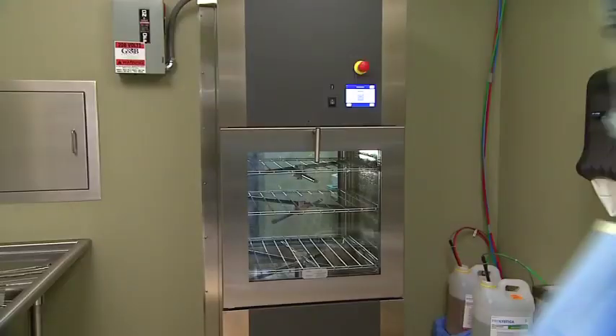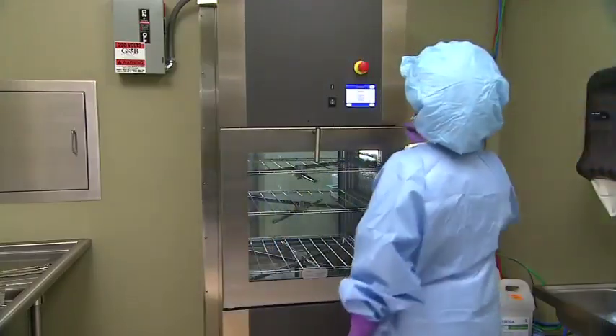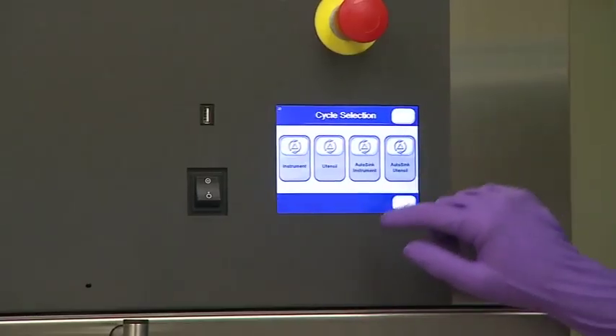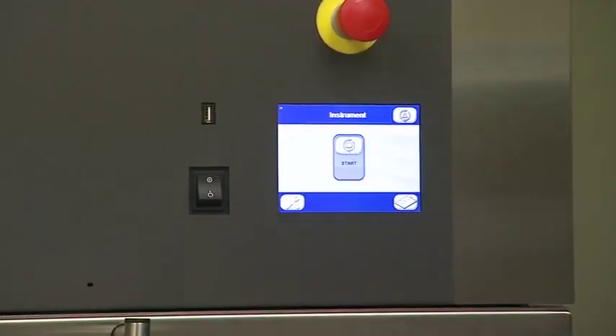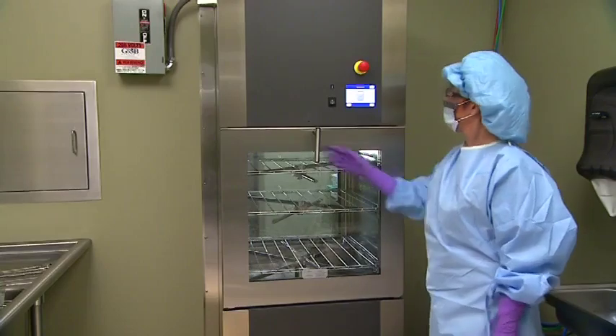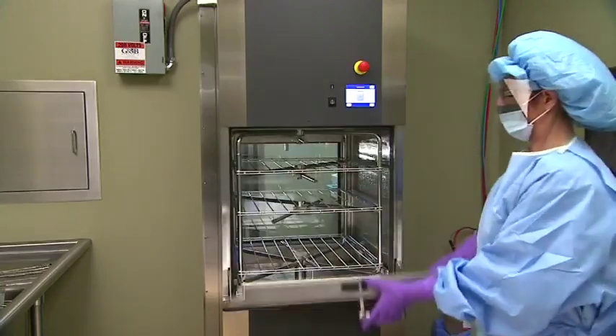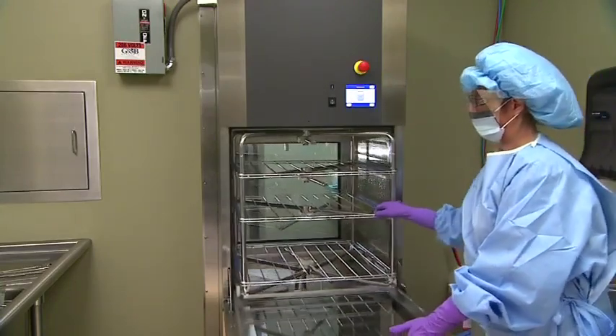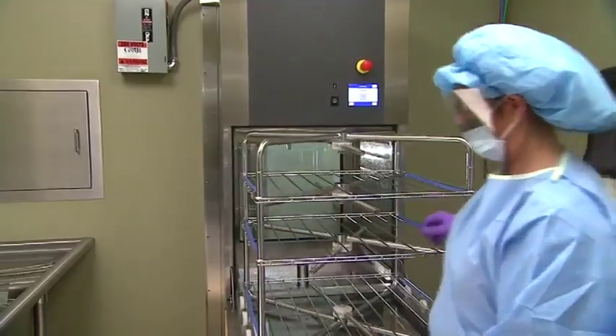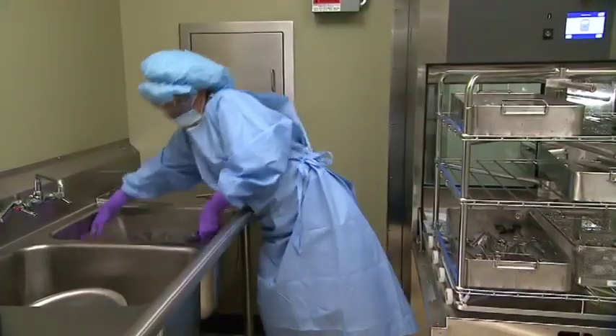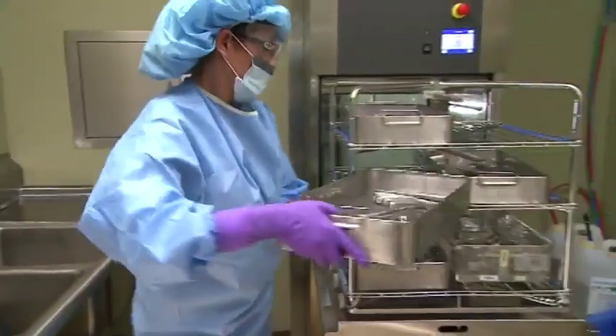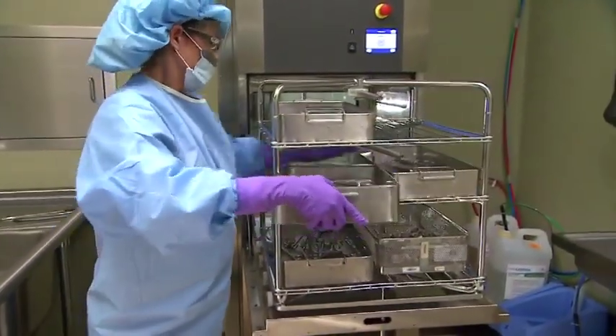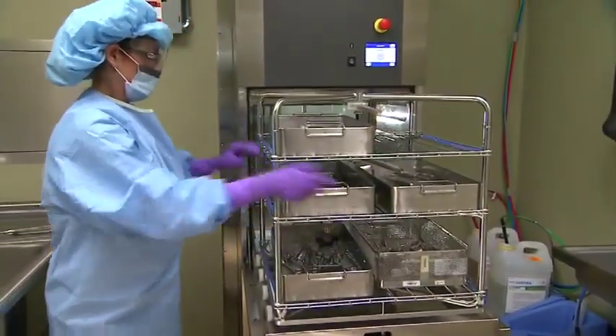Now let's get ready to run a cycle. First, ensure the appropriate cycle parameters are set in the control screen before beginning operation. Turn the door handle and open the chamber load door. Pull the manifold rack out of the chamber and onto the chamber door. Place the items to be processed onto the rack, setting larger items and trays on the bottom level.